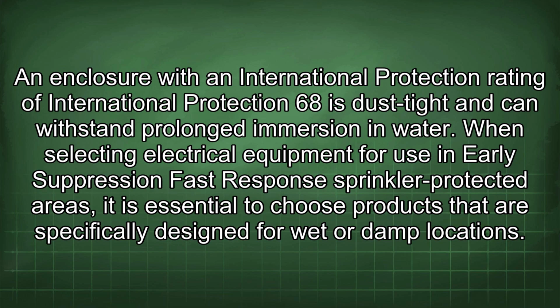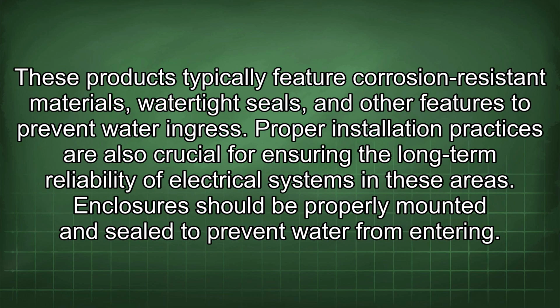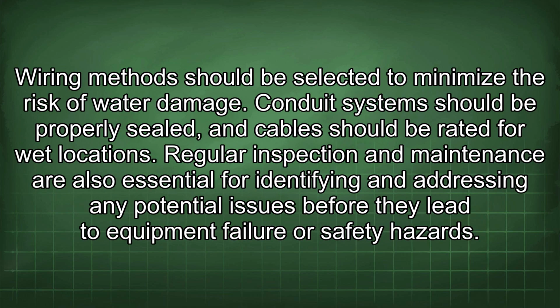When selecting electrical equipment for use in early suppression fast response sprinkler protected areas, it is essential to choose products that are specifically designed for wet or damp locations. These products typically feature corrosion-resistant materials, watertight seals, and other features to prevent water ingress. Proper installation practices are also crucial for ensuring the long-term reliability of electrical systems in these areas. Enclosures should be properly mounted and sealed to prevent water from entering. Wiring methods should be selected to minimize the risk of water damage. Conduit systems should be properly sealed, and cables should be rated for wet locations.